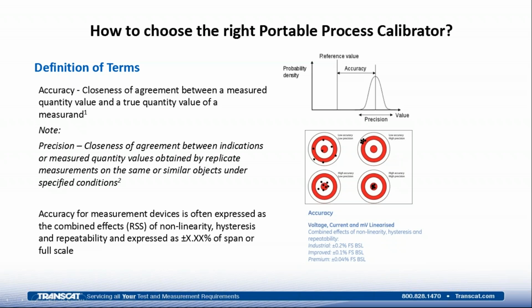Accuracy for measurement devices is often expressed as the combined effects of nonlinearity, hysteresis, and repeatability, and is expressed as a given percentage of span or full scale. Sometimes also as a percent of reading, although you don't see that as commonly for devices. Percent of reading is a more accurate or more stringent definition, and more often associated with calibrators or standards. I've included an excerpt from one of our Unik 5000 industrial pressure sensor platform data sheets and how we define accuracy on our data sheet.